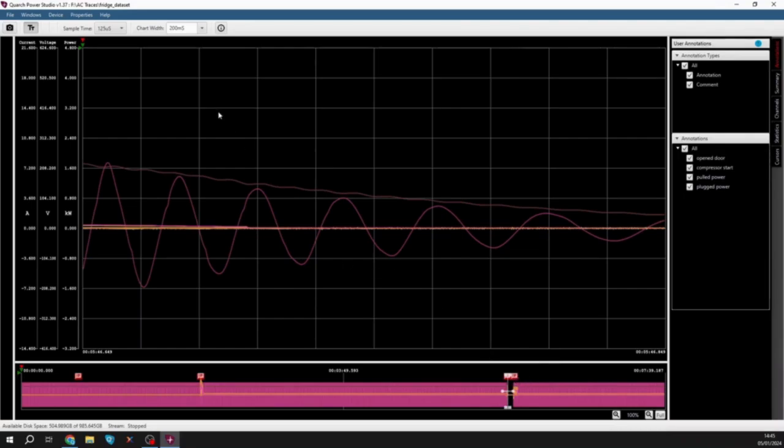Now in this case, that looks quite nice. It's a steady dropping of the voltage. However, there are cases and devices where you turn something off suddenly and you actually get a very large spike instead. And large spikes would also be seen here, and they're the kind of thing that could actually cause damage to products over time, and are very useful to be able to see at this level of resolution.